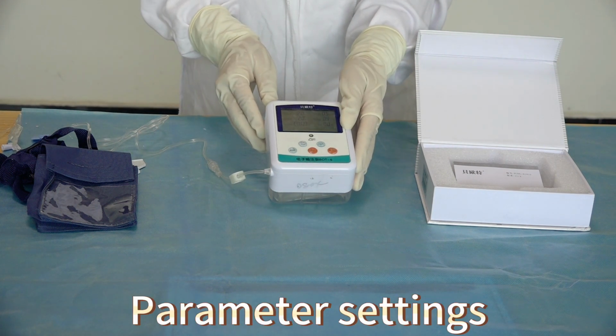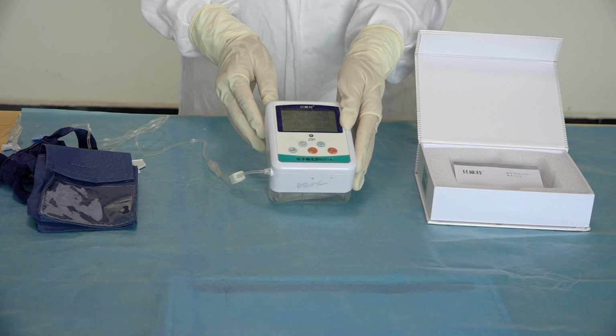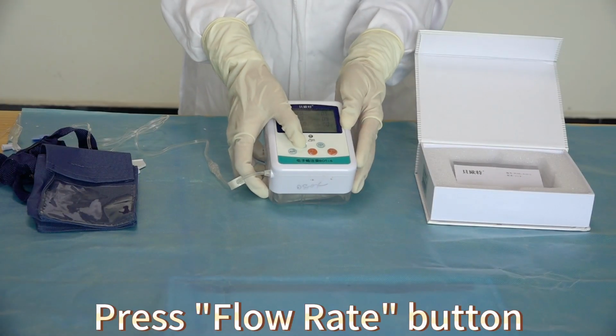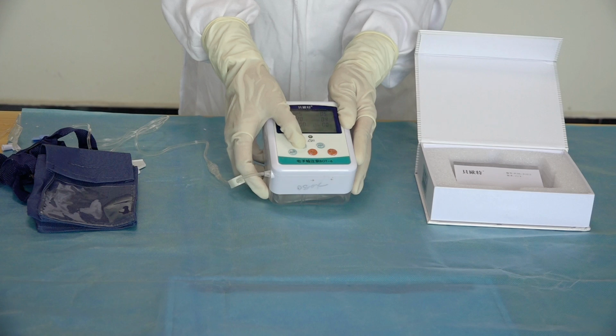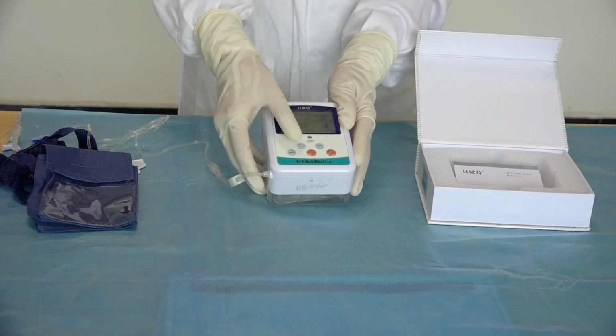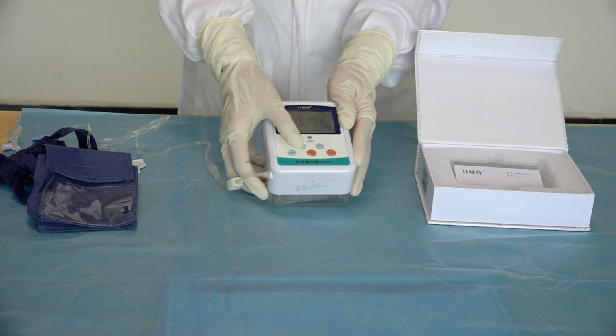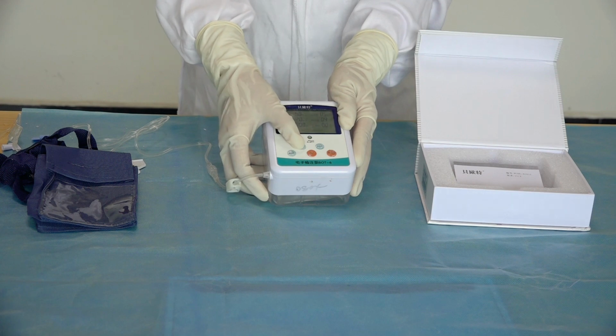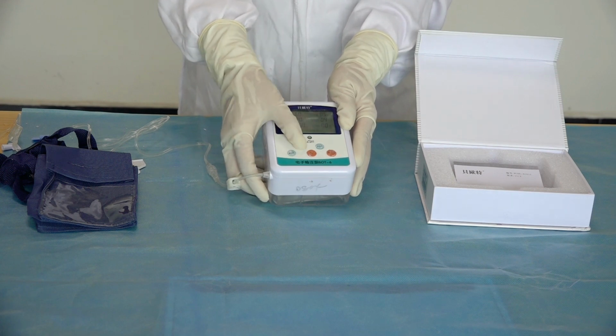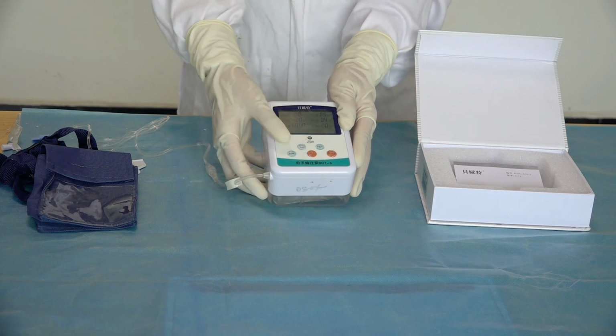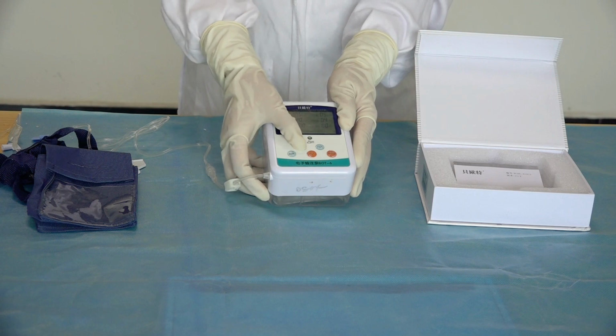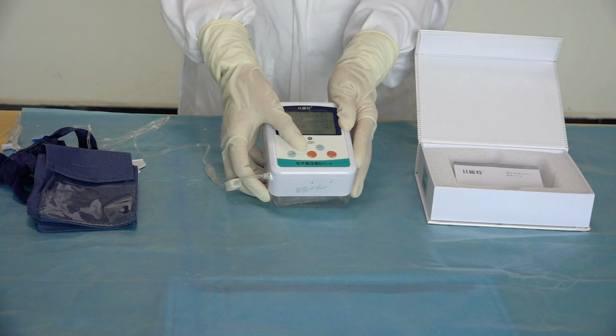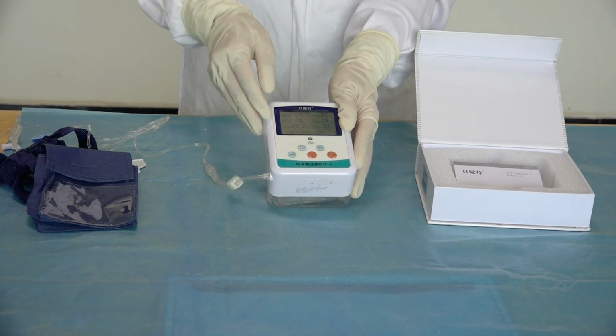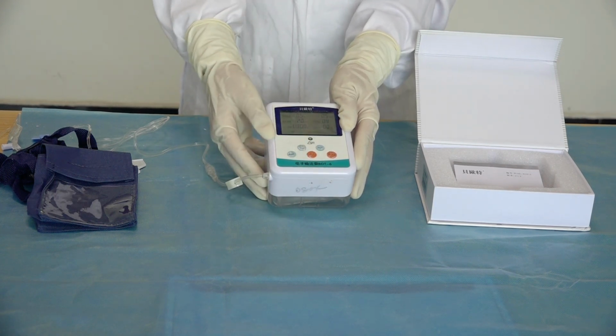Step 6. Parameter settings. Press the flow rate button in the unlocked state to set flow rate within the range of 0.5 to 9.9 ml per hour. Press this button once to increase the flow rate by 0.5 ml per hour, but an increase of 0.4 ml per hour from 9.5 ml per hour to 9.9 ml per hour.